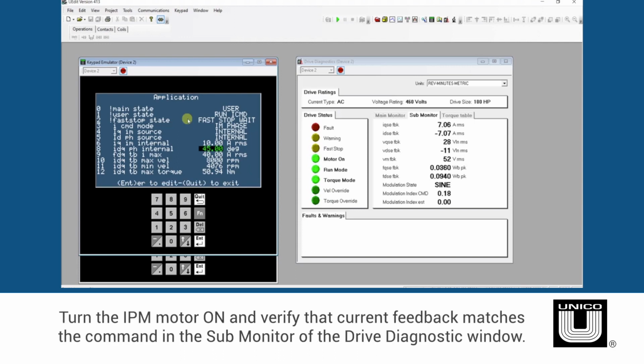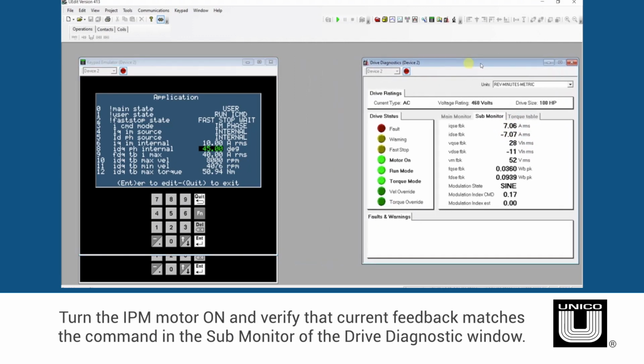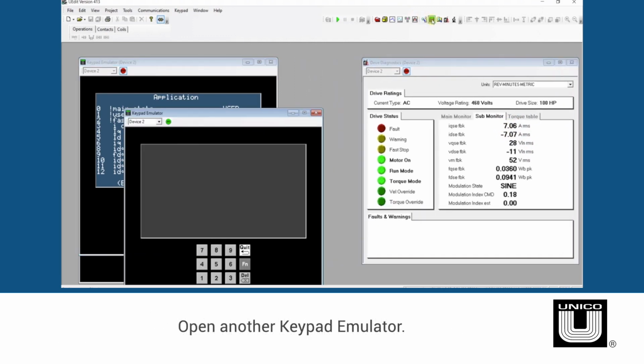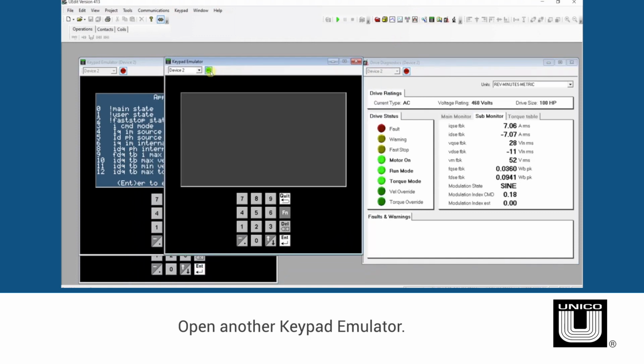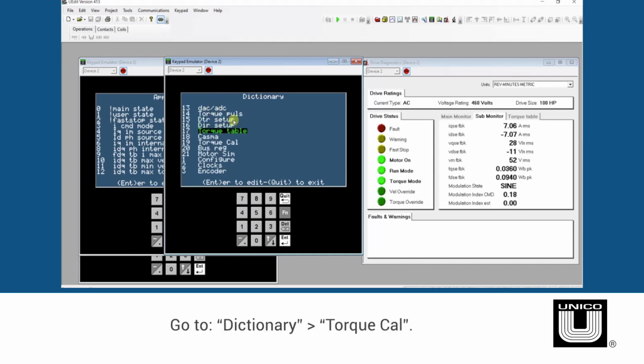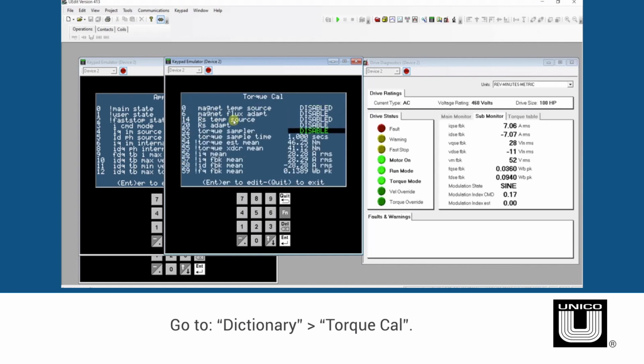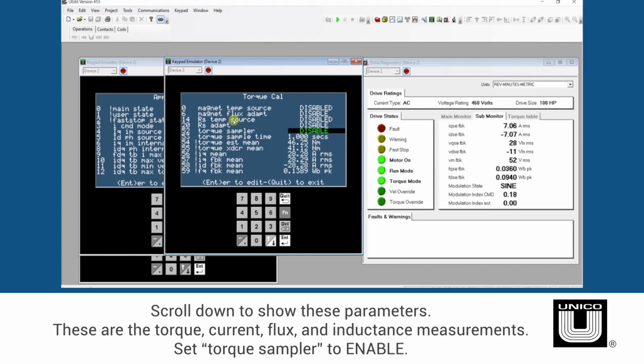Turn the IPM motor on and verify that current feedback matches the command in the sub-monitor of the drive diagnostic window. Next, open another instance of the keypad emulator. Go to Dictionary, then scroll down, then go to TorqueCal, and scroll down until the following parameters are shown on the screen. These are the torque, current, flux, and inductance measurements.